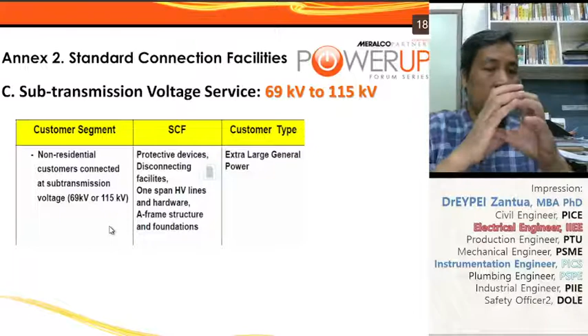Okay, so for lower voltage, for example, they need 2 megawatts. 2 megawatts, no? Okay, 2 megawatts. If the voltage is 230 volts, imagine the size of the wire. Imagine the size of the wire. That is too big. No, that's why it will go down to several panels before it will be down to lower voltages.